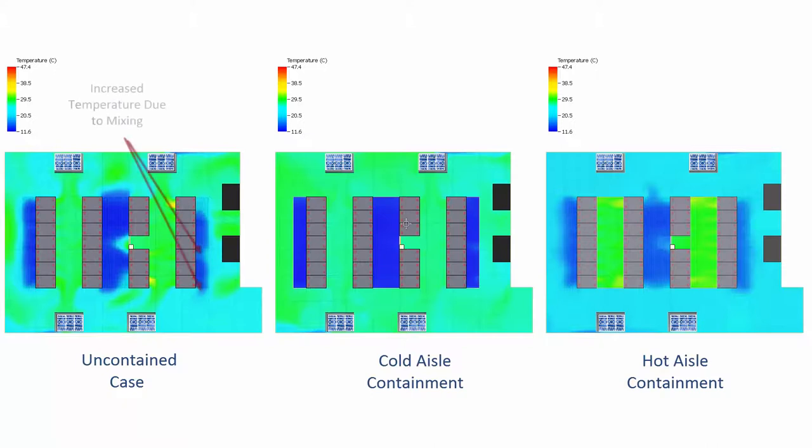Looking at the temperature variation within the room at a height of 1 meter off the floor, we see that within the uncontained system, mixing increases the air inlet temperature of some of the equipment, especially at the end of the aisles. The cold aisle contained system maintains a constant low temperature at the equipment's inlets. As a result, the cooling systems can be set to a higher temperature and still supply the equipment with air at safe operating temperatures. This saves energy and improves overall efficiency.